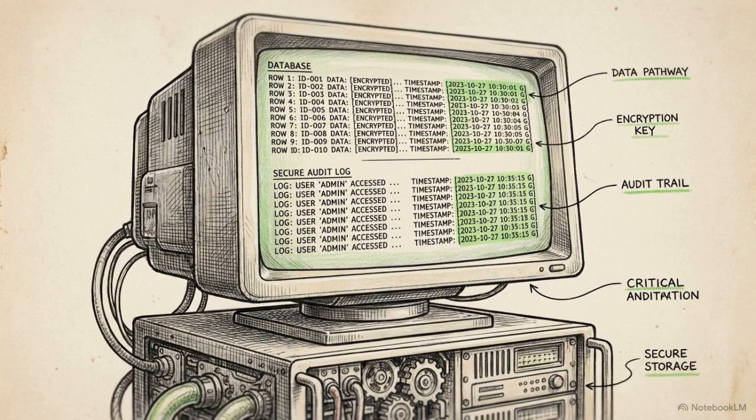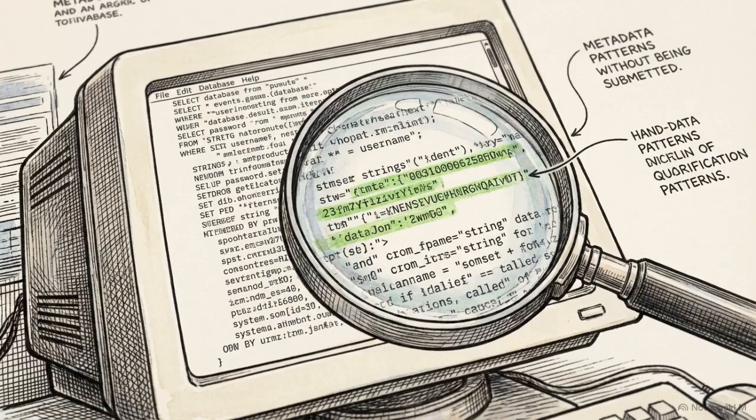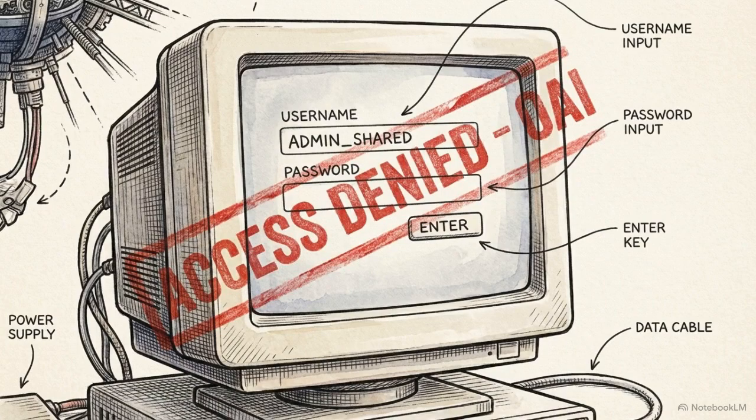The second domain covers data integrity and advanced metadata verification. FDA auditors are now deploying advanced analytics to parse digital audit trails for specific metadata patterns. Disabling audit trails or using shared logins compromises the original records mandate and triggers an official action indicated status.